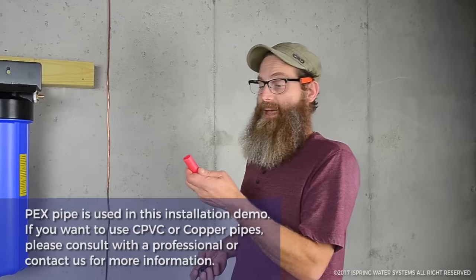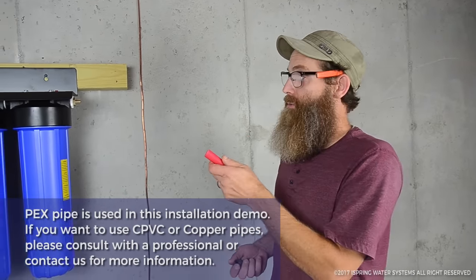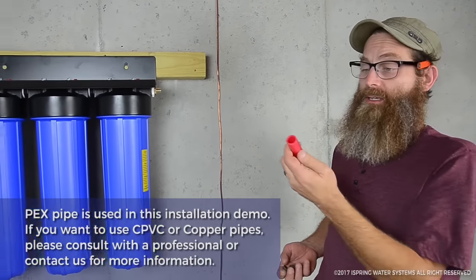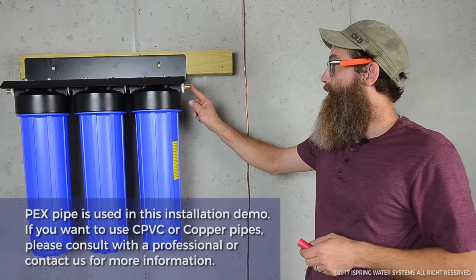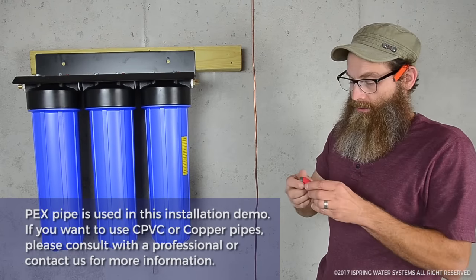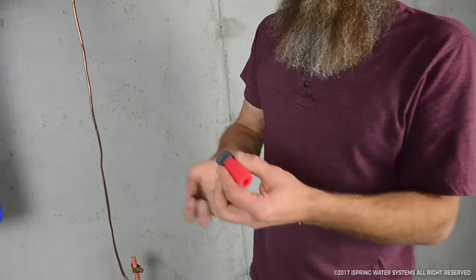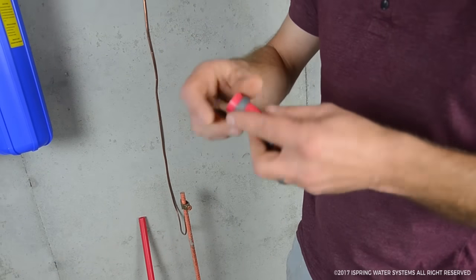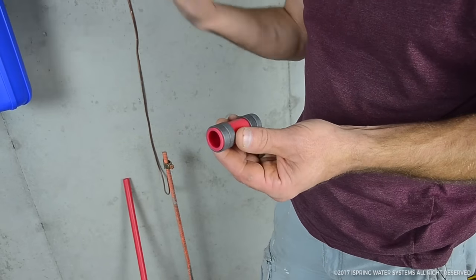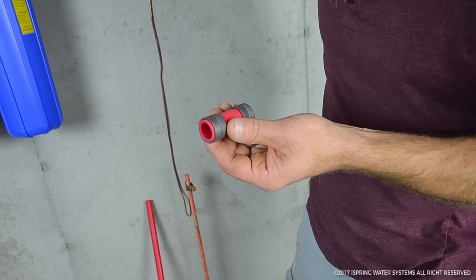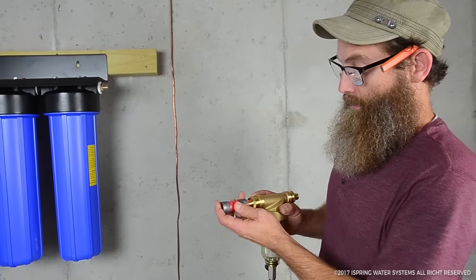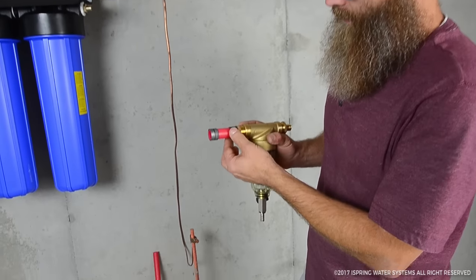So I have PEX that we're using on this job because the plumbing that comes into the house is PEX and we're sticking with that. And we have an adapter from the one inch down to three quarter of an inch. So with the PEX you can use one ring or two rings when you do the crimp on these. I like to use two because it gives you twice as much surface area so it's a lot less likely to leak. And we push them in like this and then crimp it.